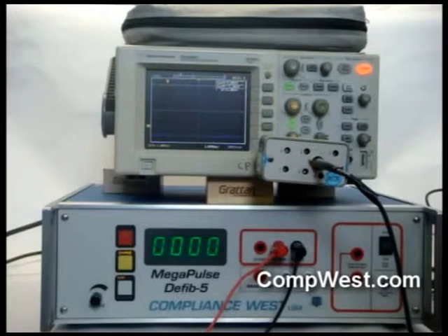We use a Tektronix P6015 1000-to-1 oscilloscope probe which has sufficient frequency response to capture the waveform accurately. If you are using a different 1000-to-1 probe, please be sure it has a frequency response equivalent to the P6015 of 75 MHz minus 3 dB and a minimum voltage rating of 5 kV.